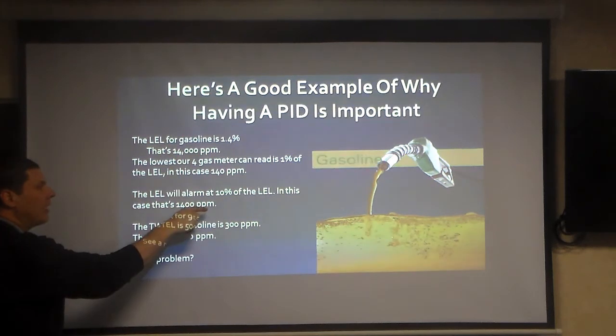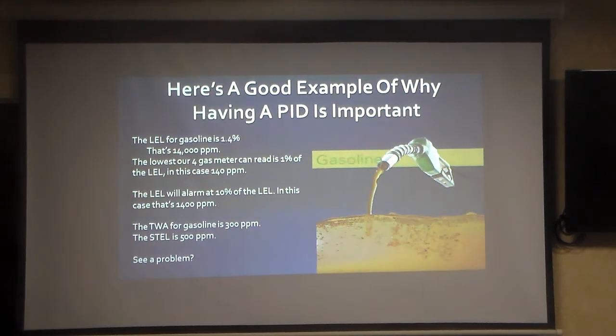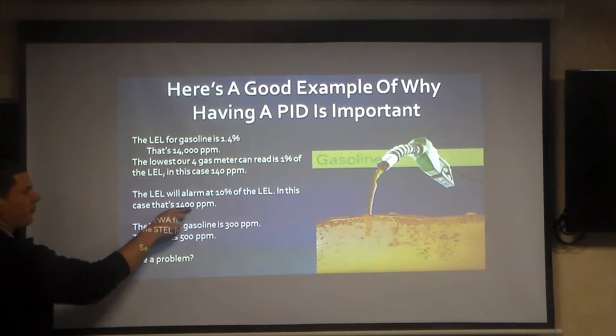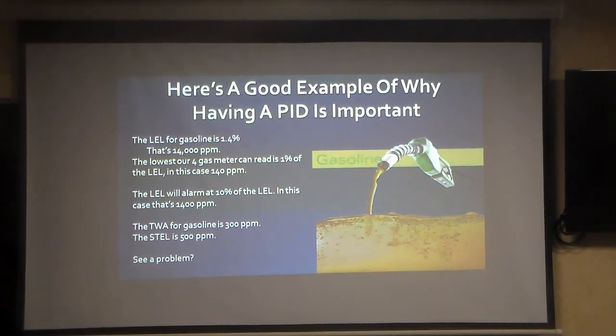The LEL will alarm at 10% of this. That's when the LEL alarms at 10%. It'll go beep, beep, beep, beep, or whatever it does. So 10%, which is 1,400 parts per million.